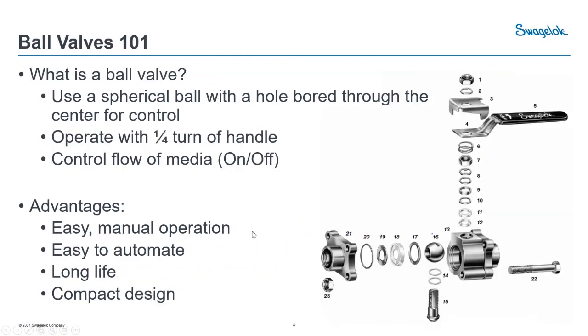We'll start with Ball Valve 101. On the right we have an exploded view of one of our 60 series ball valves. A ball valve uses a spherical ball with a hole bored through the center for on-off control of your media — basically just turning things on and off. That ball, numbered 16, turns side to side to open and close the flow path. It's a quarter turn, as opposed to a needle or gate valve which requires multiple turns to get full open. You can have fast on and off by just hitting the handle and doing a quick quarter turn.